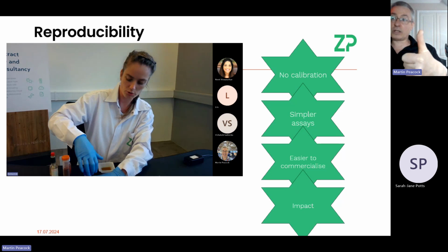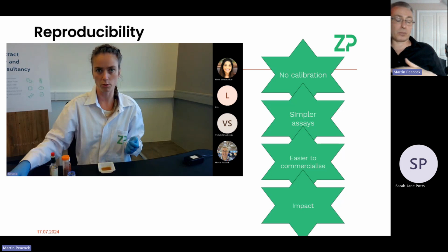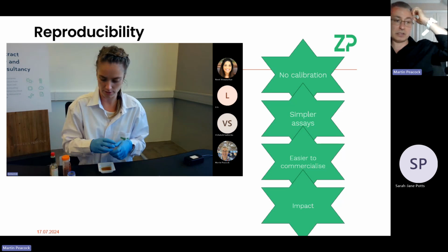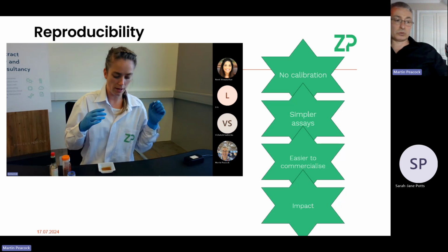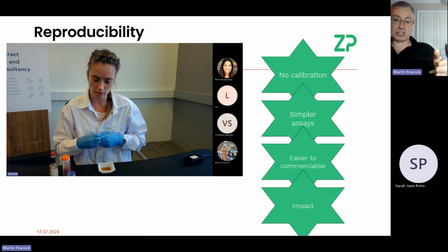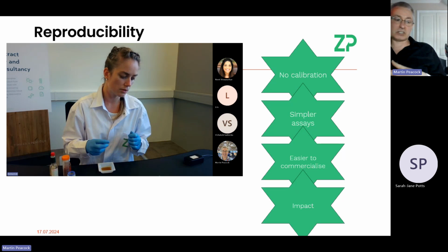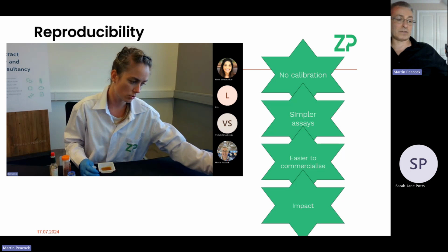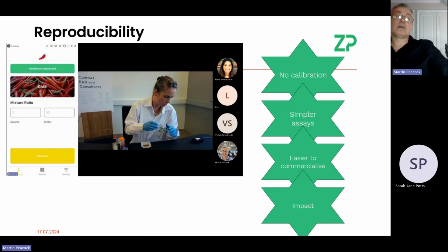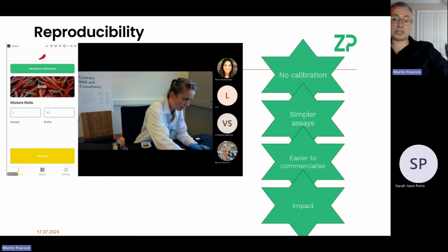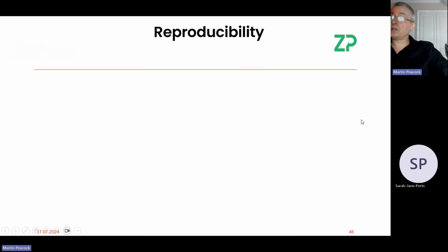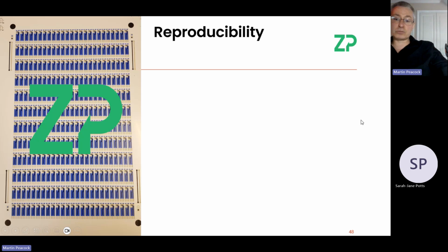But by giving high quality, it suddenly removes one of the problems that is otherwise facing people in the biosensor development world, which is actually sensor to sensor variation. And because of sensor to sensor variation, they end up trying to do calibration on their devices in the field. And if you do calibration on the device in the field, then you have to have more complex microfluidics. You're starting to have calibration solutions. None of this is going to translate well, and it's certainly not going to lead to a low cost device. So at ZP, we focus more on reproducibility of screen printed electrodes.